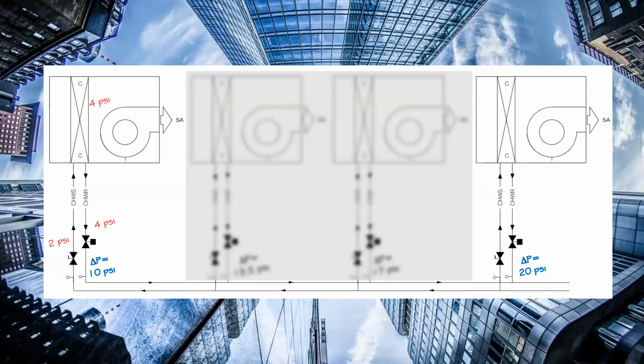As we said earlier, this far zone is typically under control. And here we see a favorable valve authority of 0.4. Perfect valve authority is 1. That is what we're shooting for. But because it's a ratio, we will never achieve a perfect 1. So we try to shoot for as close to 1 as we possibly can.